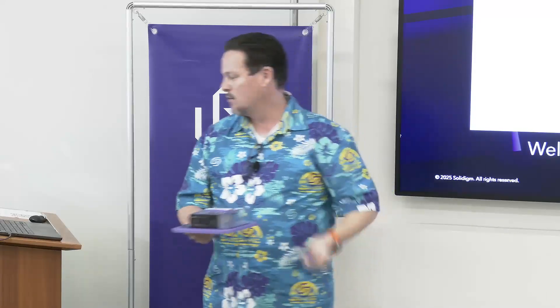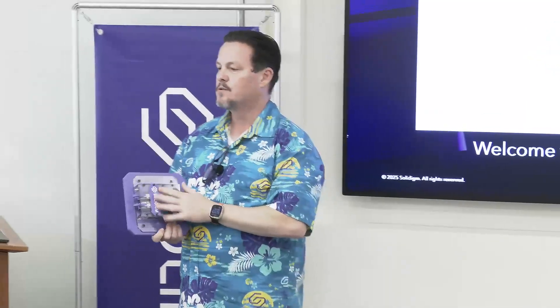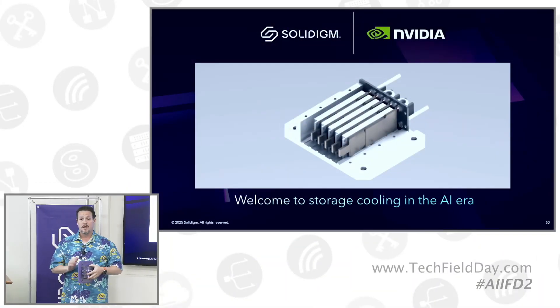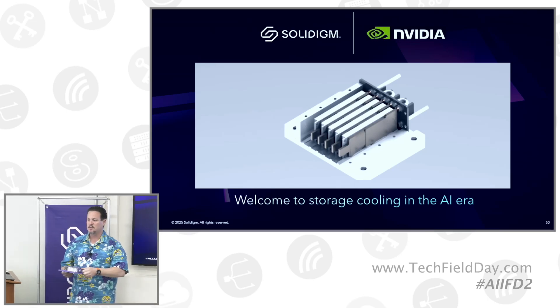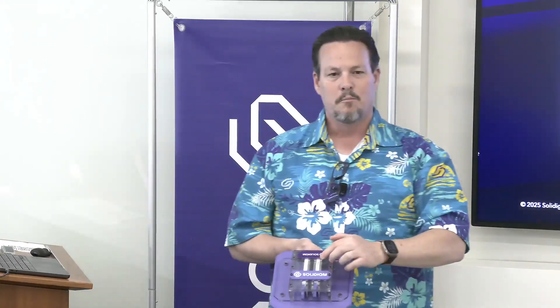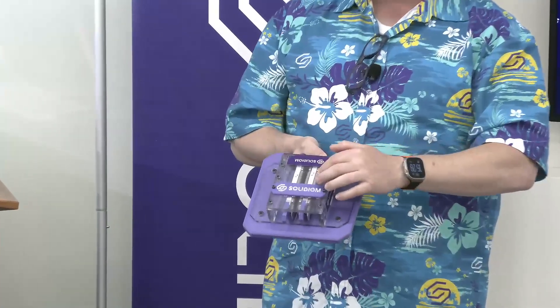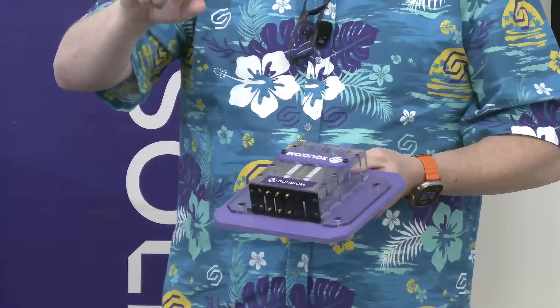You'll see here we've got liquid in-and-out ports for each of the drives. When we look at it from the other side, we have a single cold plate touching the drive. The idea of the fins is you put them on the hot side of the drive to cool it off. In order to do that, you have to have full contact generally on both sides. We designed the frame — the actual enclosure of the drive — to allow single-sided cold plate attachment. It's a spring-loaded design so that it's full contact when you put it in but still fully removable. That's why there's the hook on the drive. In production it won't be a hook, it'll be a traditional latch. The cold plate wraps the liquid flow at the hot spot on the drive.